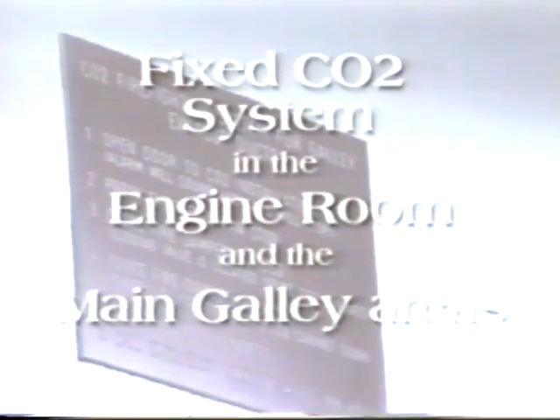There is one further firefighting system on board. This is the fixed CO2 system, located in the engine room and the main galley areas. The instructions are clearly written on every CO2 cabinet door. When you open the door, the yodel alarm will sound like this. Upon hearing this alarm, people in the compartment should vacate, because that means the CO2 system is about to be fired in that compartment.